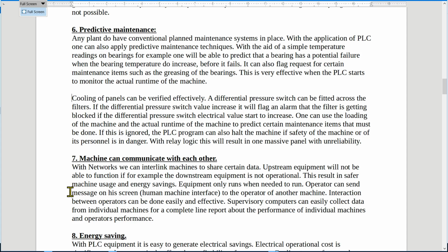Even today, the operator can send a message on his screen, on his human-machine interface, to the operator of another machine. Now, interaction between operators can be done easily and effective with these methods. No need to walk to the operator that is 50 meters away from him. He can just use the HMI to actually flag a message to the other operator. Now, supervisory computers can easily collect the data from individual machines for a complete line report about the performance of individual machines and operator performance. And it can even give you your total plant performance.